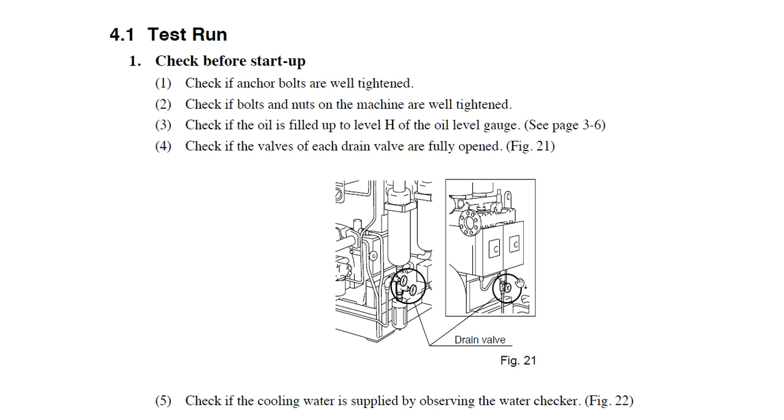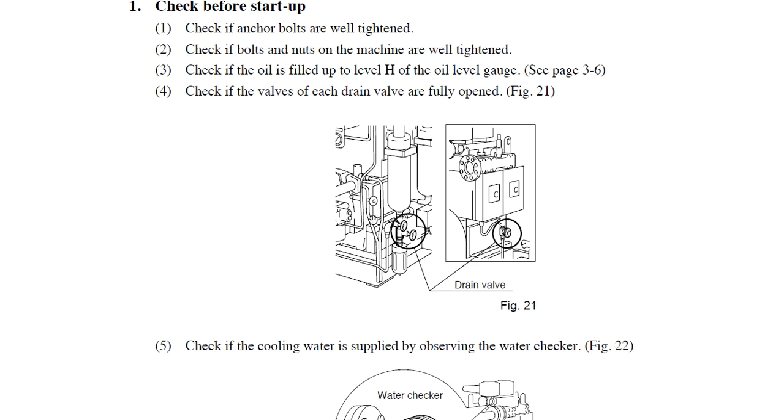When we like to make a test run, the checks: we check the anchor bolts that are well tightened. We check that all the nuts, all the bolts are tight on the machine. We have filled the oil to the high level. We have opened the drain valves shown here in the second stage and first stage.